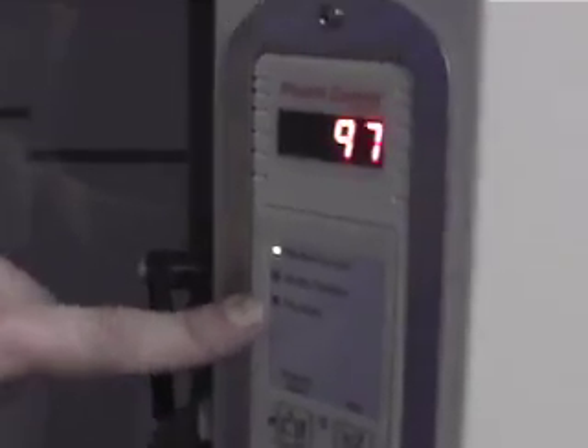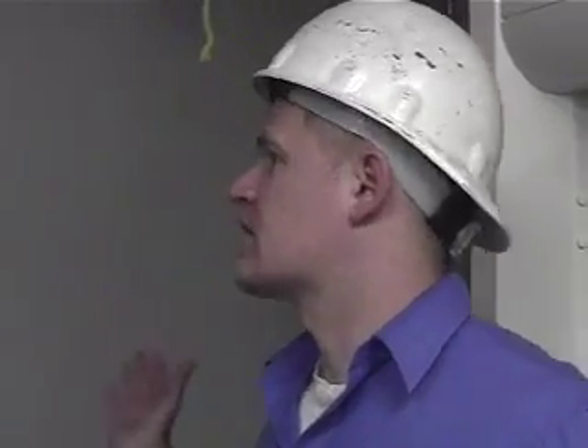Go back out, goes back into standard mode. If the pressure is not across the valve correctly, then it would actually be in flow alarm. The bottom light would be on. And you'd hear it beeping and people would be getting annoyed or they'd be pushing mute buttons. One thing lab people are very well aware of is that there's always a mute button, you push it and then everything's fine, right? Stuff's functioning just perfectly once the mute button's pushed.